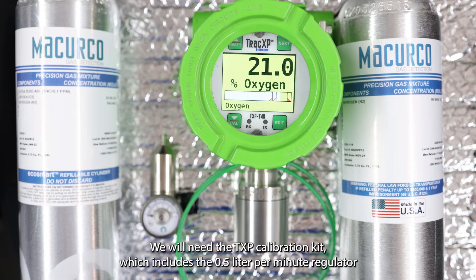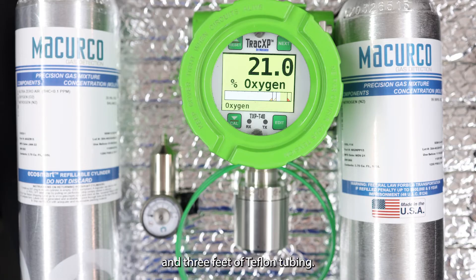To begin, we will start by ensuring we have the necessary calibration accessories. We will need the TXP calibration kit, which includes the 0.5 liter per minute regulator and three feet of Teflon tubing. We also need a bottle of 20.9% O2, often referred to as zero air, and a bottle of the target span gas — in this case a bottle of 99.99% nitrogen, also known as zero percent oxygen.